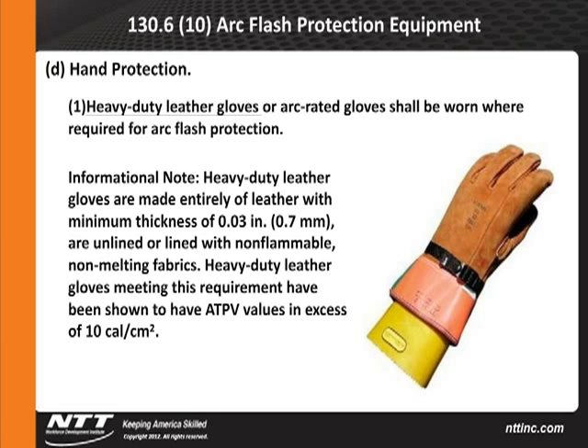Informational note. Heavy-duty leather gloves are made entirely of leather with a minimum thickness of 0.03 inches or 0.7 millimeters, and are unlined or lined with non-flammable, non-melting fabrics. Heavy-duty leather gloves meeting this requirement have been shown to have an ATPV value in excess of 10 cal per square centimeter. I've been at some places where people have been given leather gloves on the one side, and if you look at the other side, it's got this gray kind of polyester nylon in the back of it. In an arc, that's going to melt and burn.